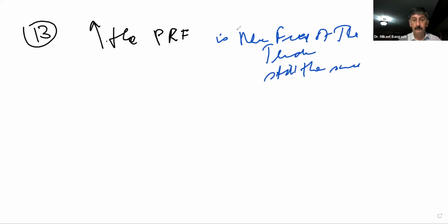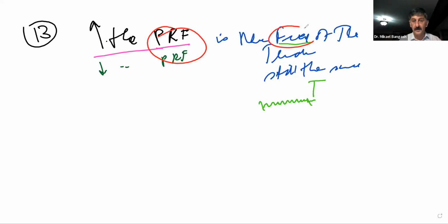And that's true. Because what was the frequency of the transducer? That is how many cycles this transducer will produce in a second. The number of cycles that are completed in that second is the frequency. But that remains the same whether you increase the PRF or decrease the PRF, because the PRF is not related to the frequency of the transducer.